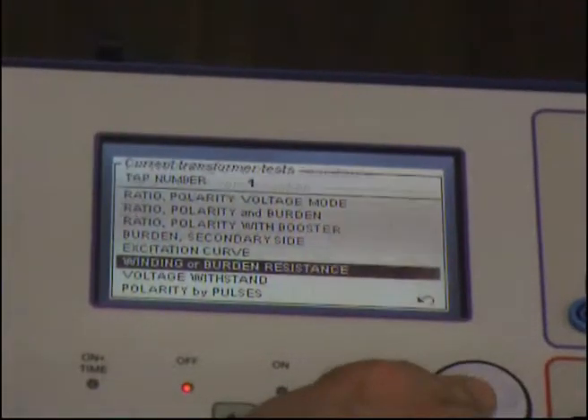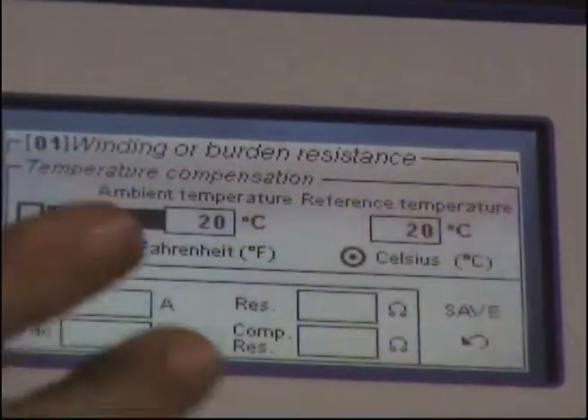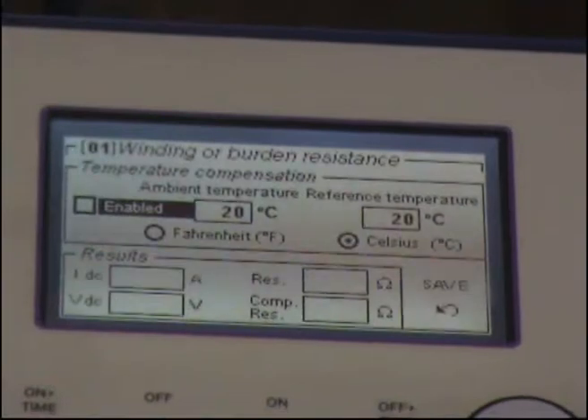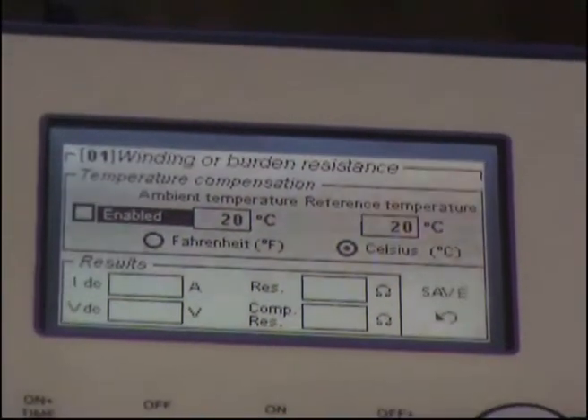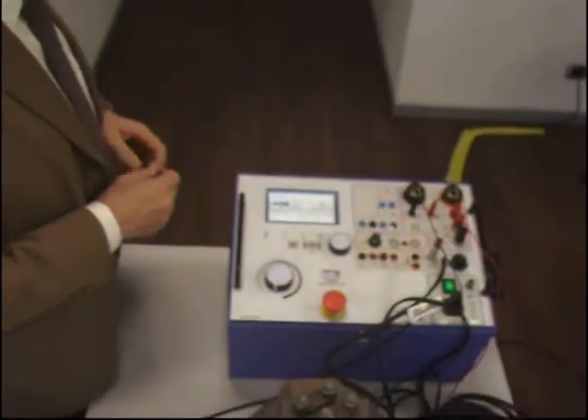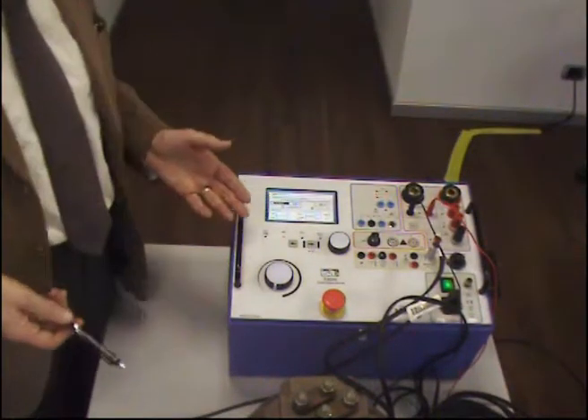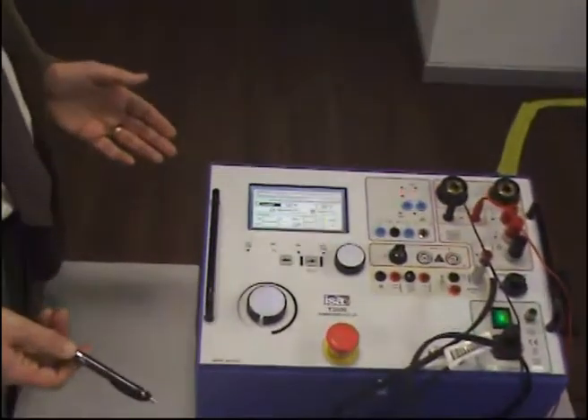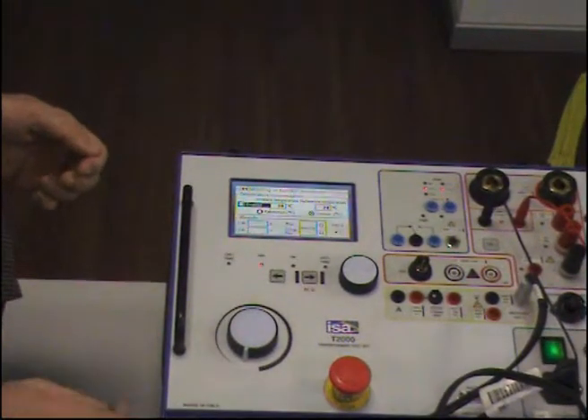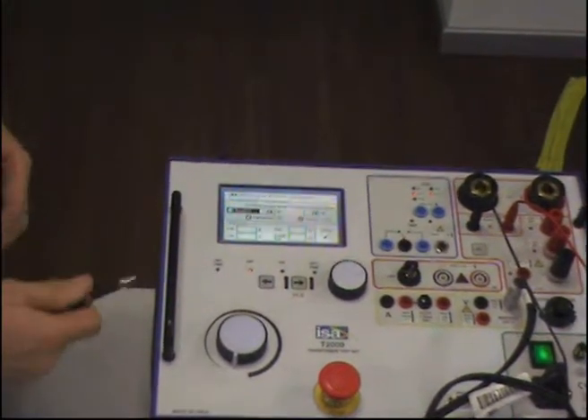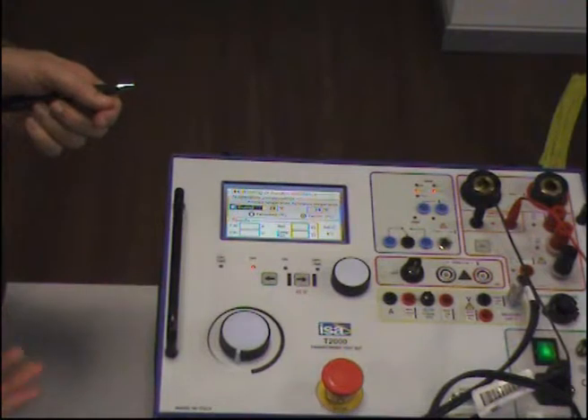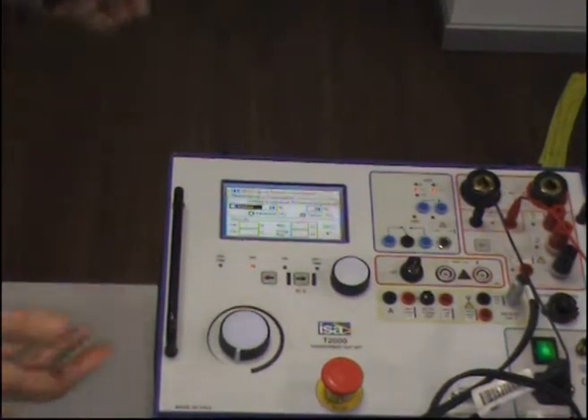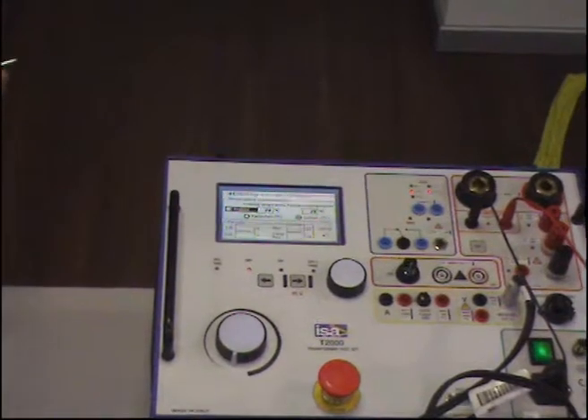Now I enter the selection and I find this first part. It is temperature compensation. What is it? Current transformers usually are operating at some 60 or 70 degrees C. And at that temperature, the resistance of the copper is changing very much, and the resistance that you measure in the real operating situation is much more than you could be measuring now, because now we are here at 22 degrees C.